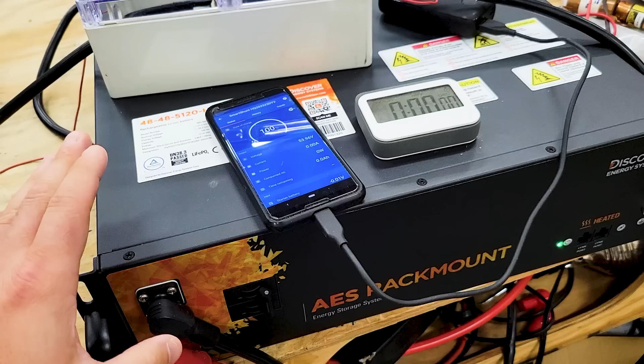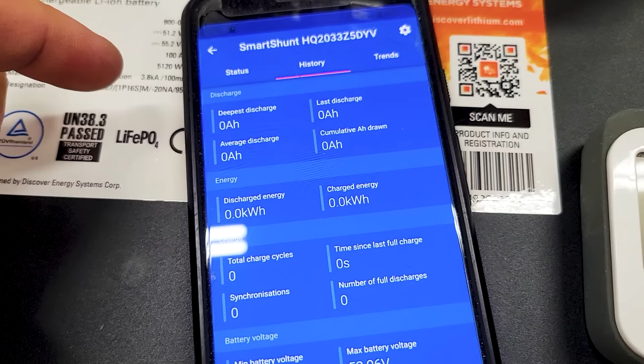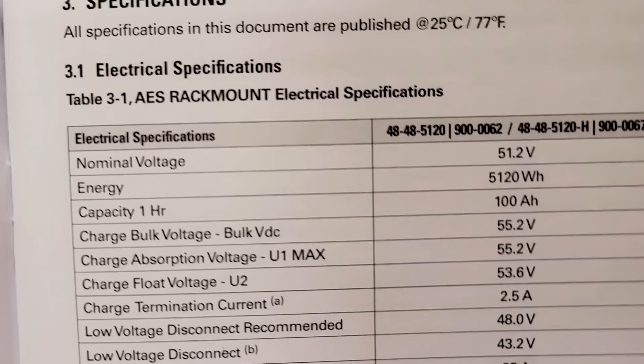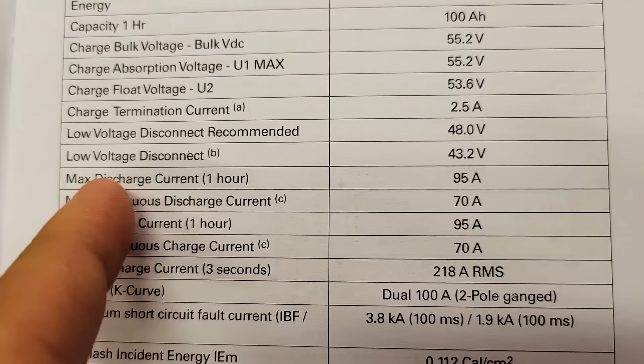I just finished charging this battery. It is fully charged and ready to go, sitting at 100%, and I reset the history so we're all at zeros. Now if we check the specifications in the manual, the maximum discharge current for 1 hour is 95 amps. So let's try that. We'll turn on the inverter.